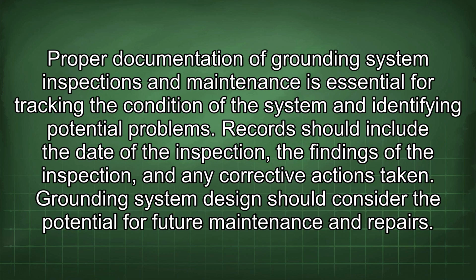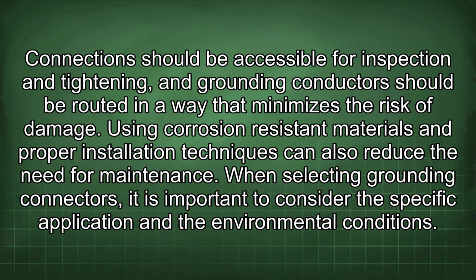Proper documentation of grounding system inspections and maintenance is essential for tracking the condition of the system and identifying potential problems. Records should include the date of the inspection, the findings of the inspection, and any corrective actions taken. Grounding system design should consider the potential for future maintenance and repairs. Connections should be accessible for inspection and tightening, and grounding conductors should be routed in a way that minimizes the risk of damage. Using corrosion-resistant materials and proper installation techniques can also reduce the need for maintenance.